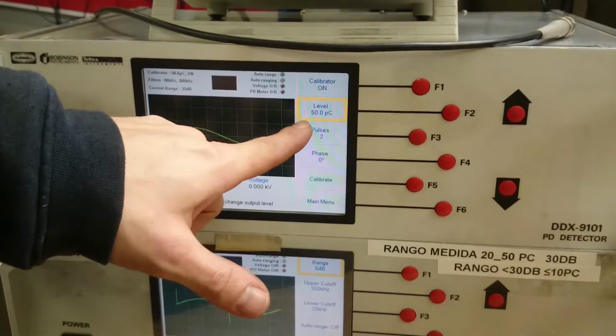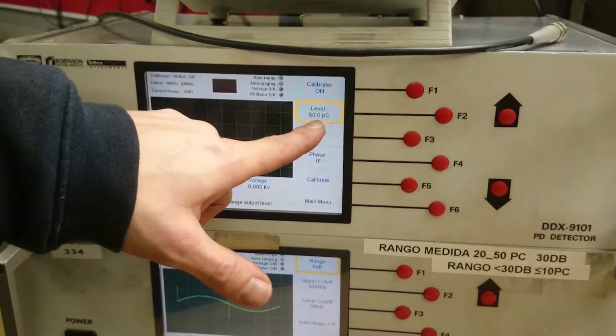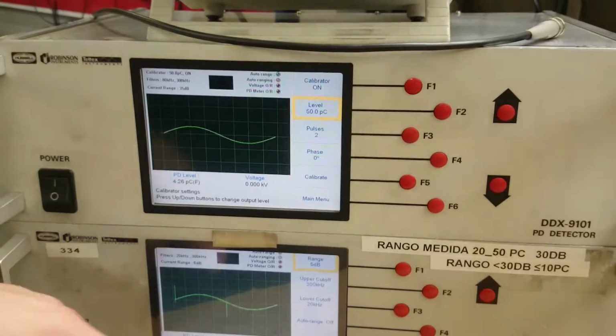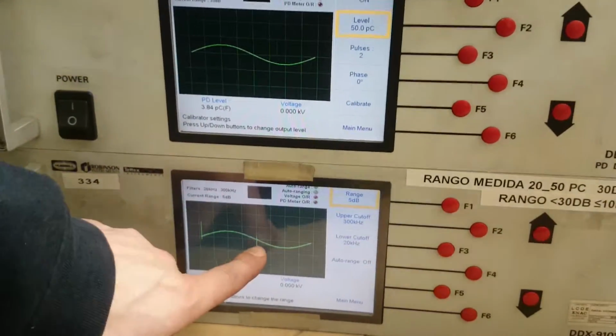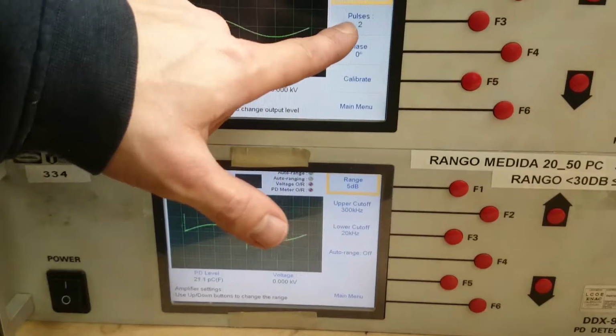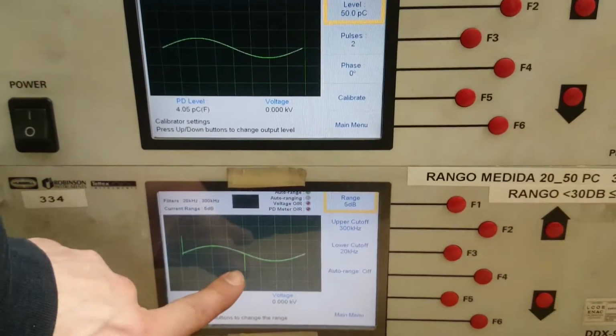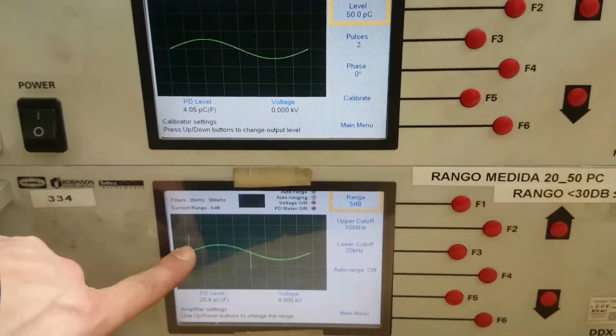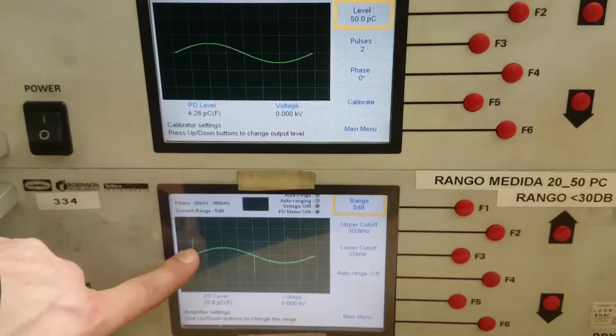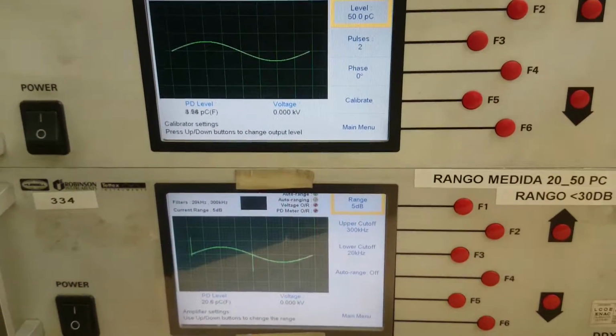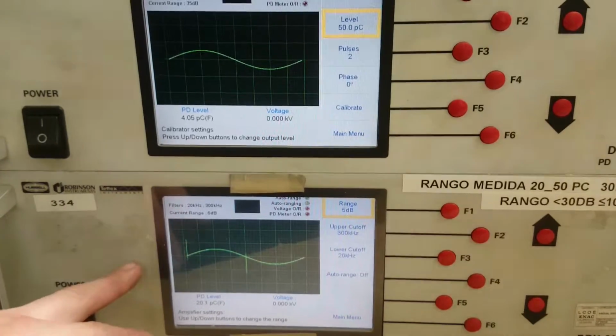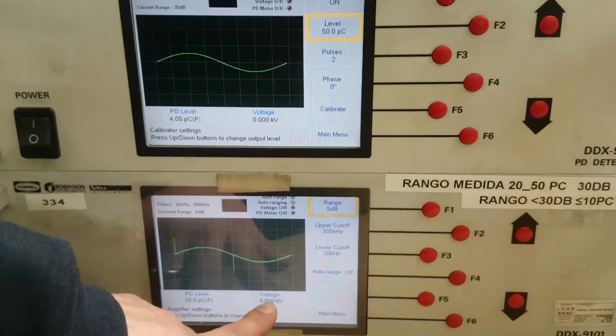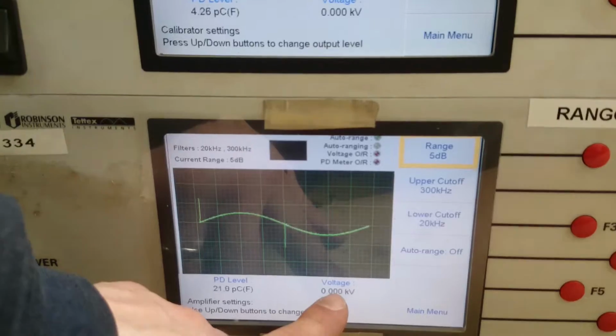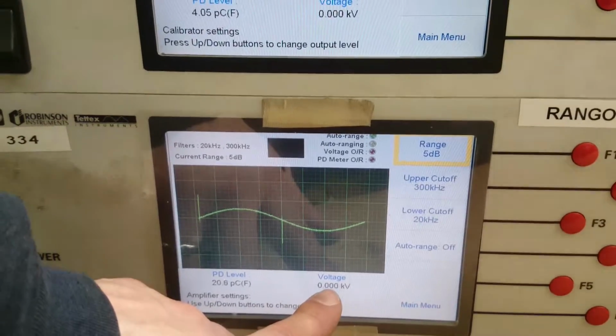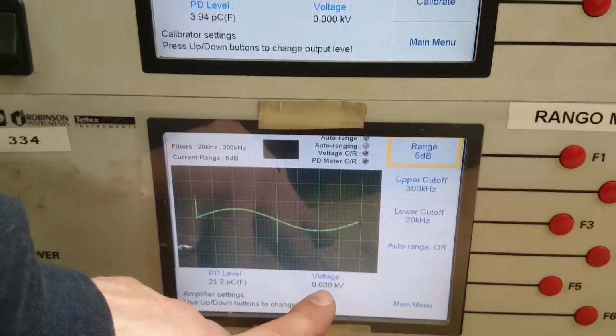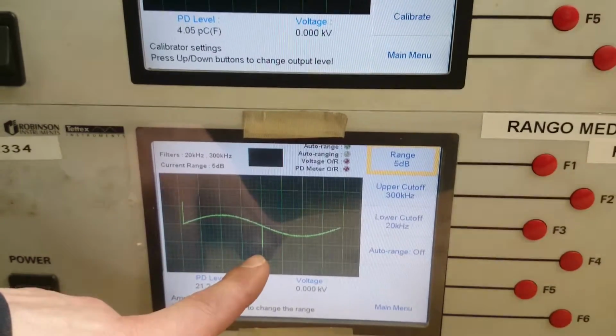The calibration output of the top one is set to 50 pC. That's looped into the back into this one, and you can see the two pulses there. That's set to 2 pulses, and you can see the 2 pulses there and there, and they're still not moving on the phase, which means that they're referenced to the mains frequency. The kilovolt meter is 0, so it can't reference to the input frequency. It's got to reference to the mains supply frequency, which is why they're still.